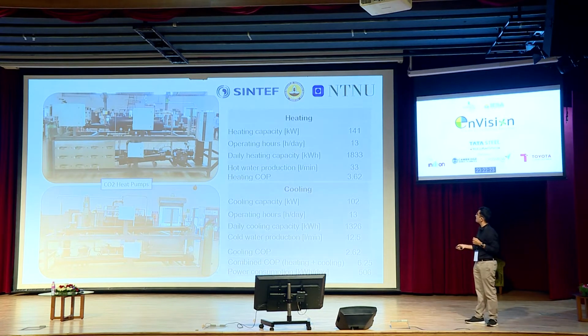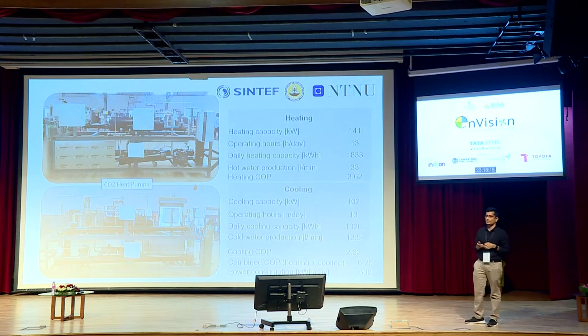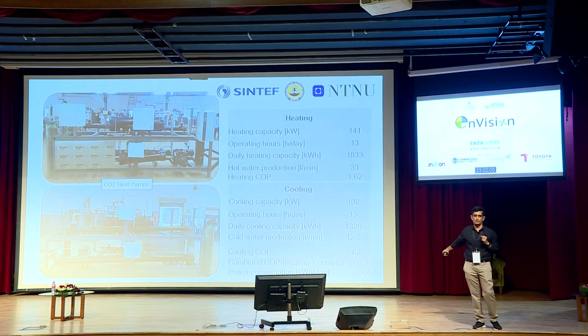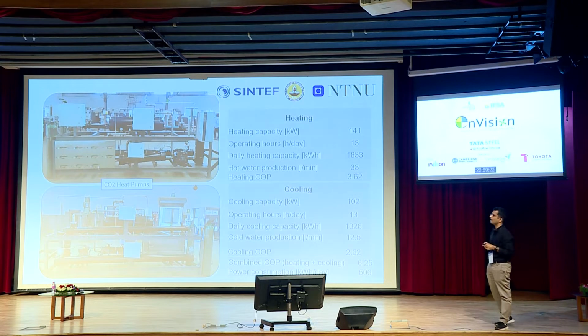A single system can deliver hot water at almost 90 degrees C, and chilled water at almost 5 degrees C. The overall benefit, what they call combined COP, coefficient of performance, is almost greater than 6. What does this mean? For every unit of electricity I consume, I'm producing 6 units of energy. This is something we really need to benefit from.